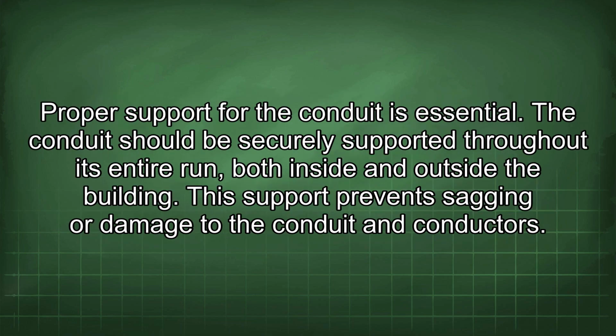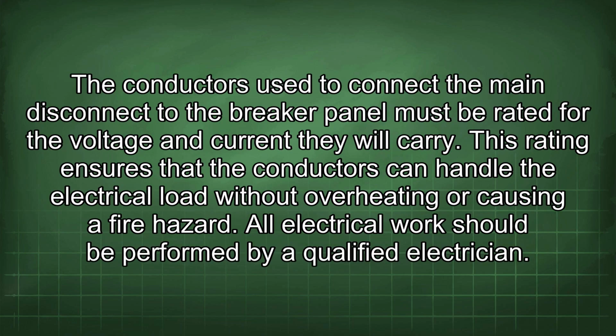Proper support for the conduit is essential. The conduit should be securely supported throughout its entire run, both inside and outside the building. This support prevents sagging or damage to the conduit and conductors. The conductors used to connect the main disconnect to the breaker panel must be rated for the voltage and current they will carry. This rating ensures that the conductors can handle the electrical load without overheating or causing a fire hazard.